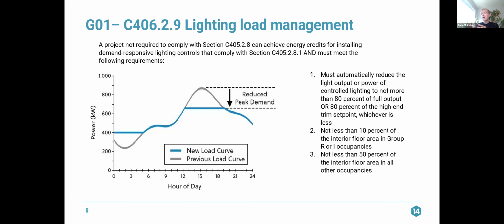Another requirement: not less than 10% of the interior floor area in group R or I occupancies has to have this lighting load management. And then not less than 50% of the interior floor area in all other occupancies is required to have this. So the idea here is that if you are a residential type occupancy, you can just have these lighting load management controls on your common spaces, the spaces that serve your residential occupancy. And then all other occupancies have to comply with 50% of their floor area.